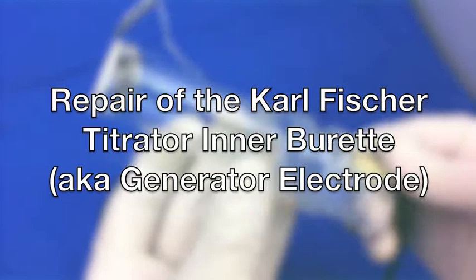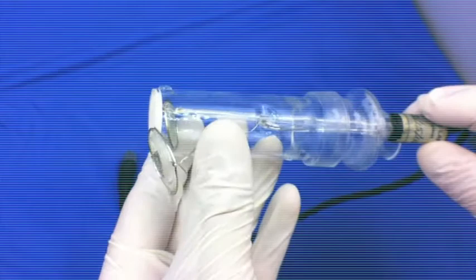This is a generator electrode, also referred to as an inner burette. As you can see, this generator electrode has been damaged where the platinum wire and screen have become detached.